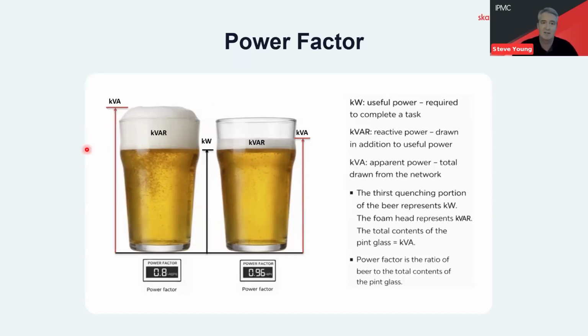Now, if we have a lot of induction motors, then we've got more reactive power. So we may see a reactive power charge appear on the bill as the power factor drops below the prerequisite level, which is usually about 0.95 lagging, as we call it. We can show this by way of a pint analogy. The useful part of the drink, which is the beer, is the kilowatts, and it's common to both pint pots.